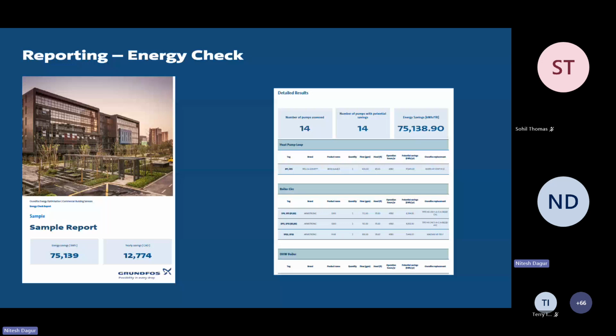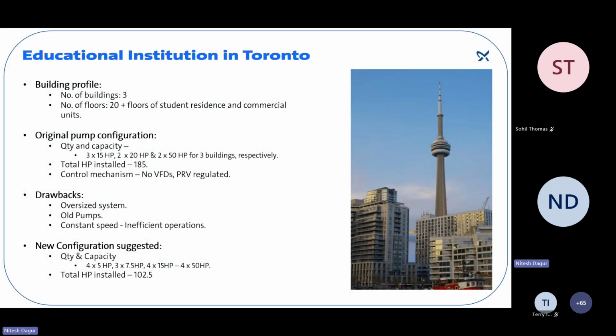Going on to the impact of this, I have a couple of case studies. This is an educational institution in Toronto, which had 3 buildings with 20-plus floors of student residences and commercial units. The original configuration of the boosters was 3 by 15 horsepower, 2 by 20 horsepower, and 2 by 50 horsepower, respectively. When we were done with our analysis and made our selections based on the cases we have collected from the field, which comprise our selection model, we suggested the customer install 4 by 5 HP pumps, 22 and a half horsepower in the second building, and 60 horsepower in the third building.